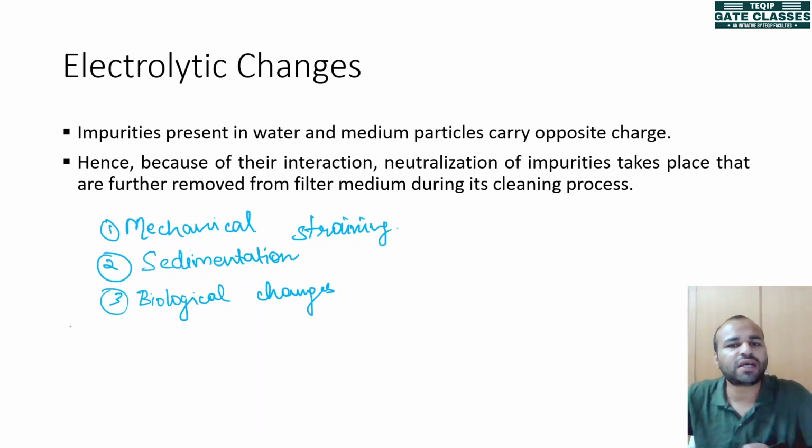Now in that biological changes, there was also a last effect, that was endogenous respiration, in which the lowest layer, consisting of the dead cells of the organic matter, of the algae and the microorganisms, was getting percolated even further into the filter medium as the water flowed, and eventually the filter medium got choked, so the process of filtration stopped, and then we have to clean the system.